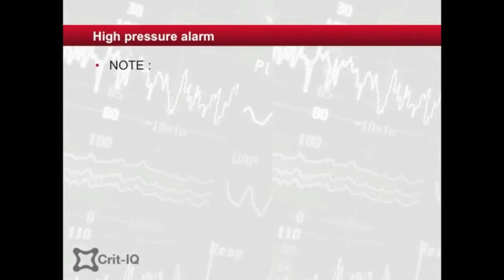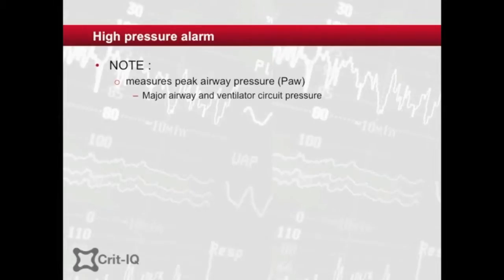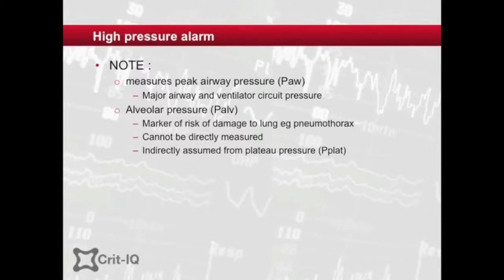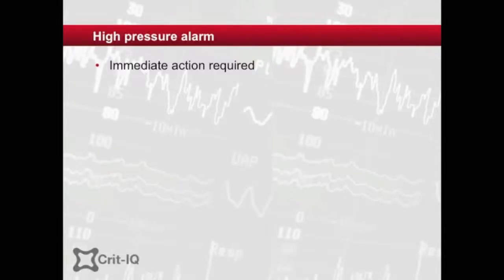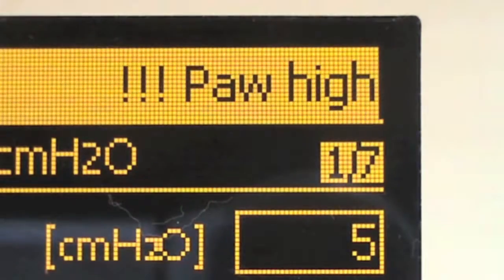It should be noted that the alarm responds to the peak airway pressure, which largely reflects major airway and circuit pressures. It does not measure effective alveolar pressure, which is more relevant to pressure-induced damage to the lungs. The list of causes includes some conditions that can be rapidly fatal. This, combined with potential hypoventilation, mandates immediate attention when the high pressure alarm is activated.